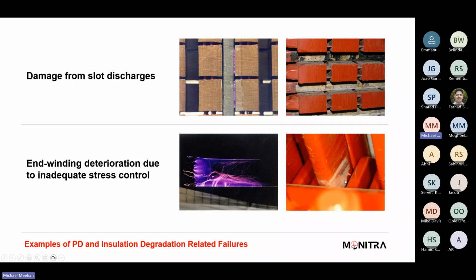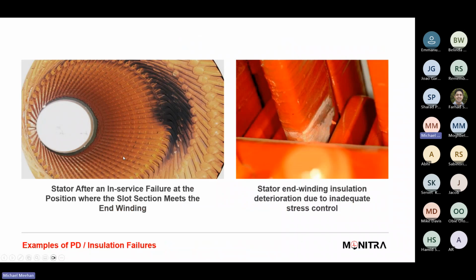And if you've got vibrations or the packing itself isn't quite what it needs to be, any movement there, you just need a bit of rubbing, and that bit of rubbing just degrades the insulation at that point, and then it starts to create PD, and then that can run away into a failure, which is obviously what you want to avoid. It's more after effects of potential issues.